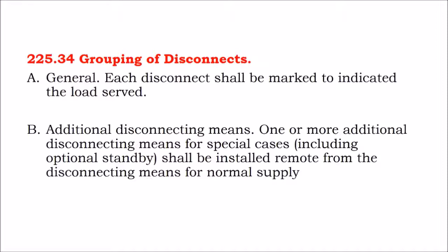And so standby switches and remote and emergency switches should be located remotely from the disconnect means for the normal supply. But then again, at the residential level, if the house is on fire, the fire department shows up, they don't want to turn the building off only to trigger the emergency power system. And usually with a generator, it's very obvious to the firemen that there's a generator on site. They can just run over to the generator and turn off the generator disconnect as well. But what that means is, when you get to where's the disconnect on your battery system, on a grid connected battery, is that disconnect going to be located remotely, or is it going to be located right next to all the other services? I think we're really splitting hairs here.